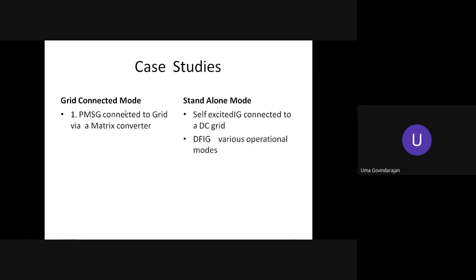In the case of PMSG, when the wind speed varies, the generated voltage will have variable amplitude and variable frequency. So this variable amplitude and variable frequency you cannot directly give to an AC load. The power has to be conditioned before being given to the load. Therefore, the variable voltage, variable frequency should be converted into constant voltage and constant frequency. The power can be different, but it produces a constant voltage and constant frequency. So it inevitably uses a power electronic converter in between the generator and the grid. We have n types of power converters and different combinations of power converters.